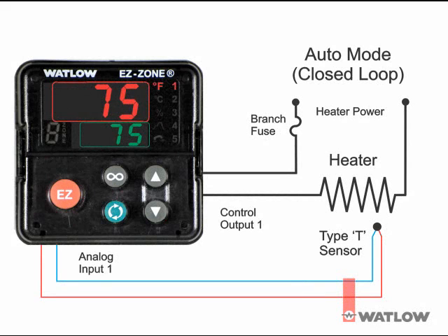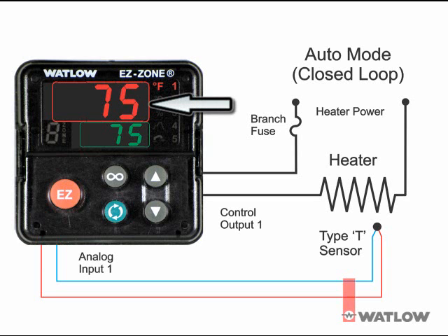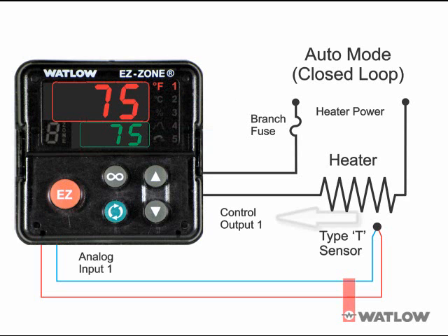In auto mode, the controller monitors the sensor input to determine if closed-loop control is possible. In this diagram, a type T thermocouple monitors the temperature of a heater. The controller checks to make certain a functioning sensor is providing a valid input signal. Assuming the user requested auto mode and a valid analog signal is present, the controller will perform closed-loop control. Closed-loop control uses the process sensor to determine the difference between the process value, shown here in red on the upper display, and the closed-loop setpoint, shown here in green on the lower display. The controller applies or removes power to a control output to reduce the difference.